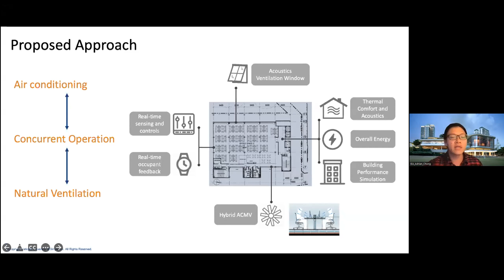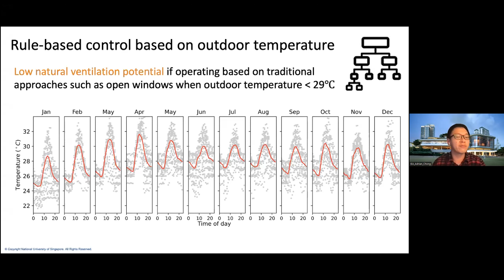Just for background, if we look at rule-based control based on outdoor temperature, this is typically what's recommended in the literature for mixed mode. In Singapore, given our climate, if we open windows only when outdoor temperature is less than 29 degrees Celsius, our opportunity to operate in natural ventilation is only around 10%. So that's not very much.